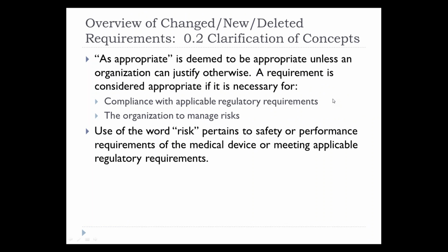Section 0.2, entitled Clarification of Concepts, states that whenever you see "as appropriate" in the normative requirements of the standard, the requirement is deemed to be appropriate unless you can justify otherwise. Keep in mind, however, that a requirement is considered appropriate if it's necessary for you to comply with applicable regulatory requirements or for you to manage risks. Then it always has to be appropriate. They clarify that use of the word risk pertains to safety or performance requirements of the medical device or meeting applicable regulatory requirements.